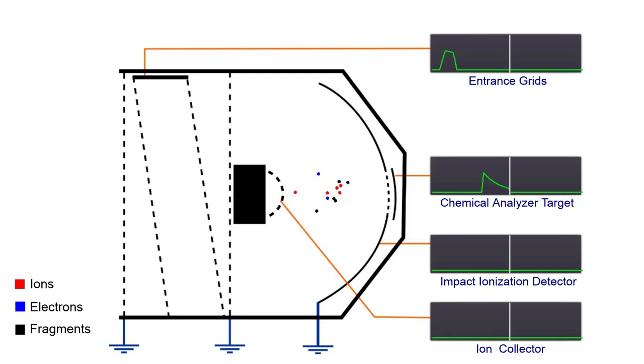Ions will be attracted by the ion collector. Since the attractive force is constant, the acceleration on the particle will be based on its mass, A equals F divided by M. This in turn determines how quickly the ion gets to the ion collector. So, the heavier the ion, the longer it takes. This arrangement forms what is known as the time of flight mass spectrometer.